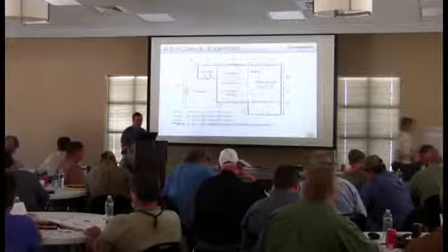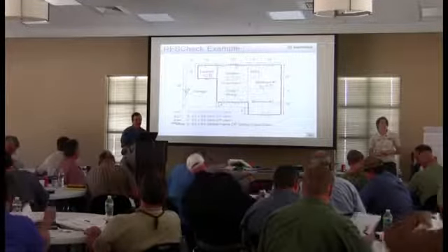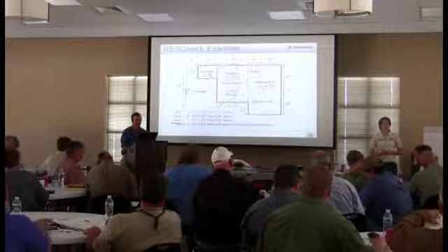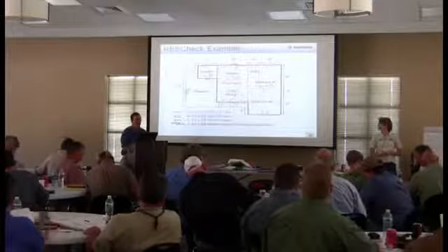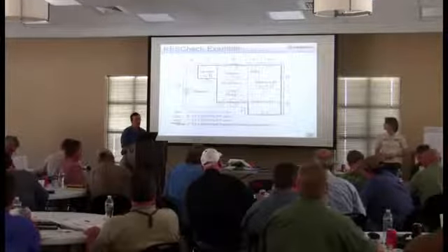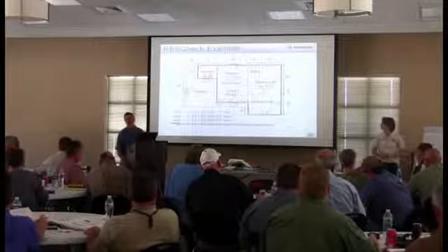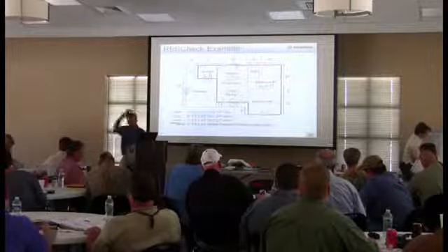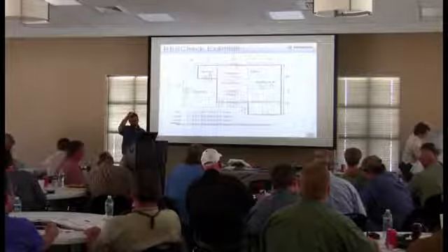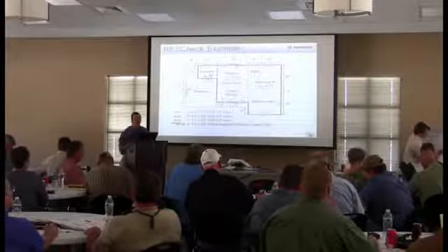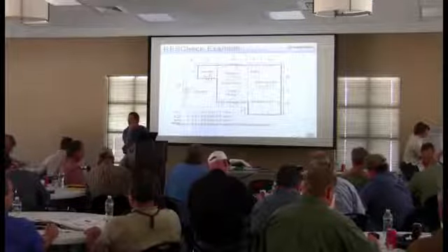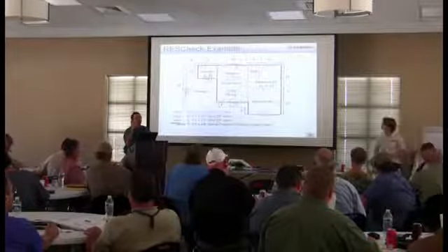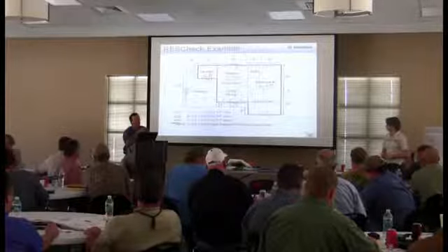We also have a solid front door, opaque door right here, and we have a door to the garage. And I'll tell you, you can usually just assume a door is 20 square feet. It's awful close to 20. If it's not exactly, I can live with it. So assume doors are 20 square feet. So we have 2 solid doors. All right, what we just did was the hardest part of this. That was the hardest part, is getting all the takeoffs.